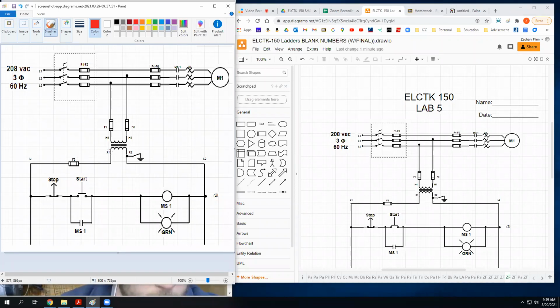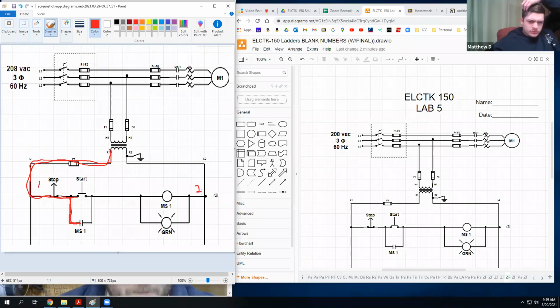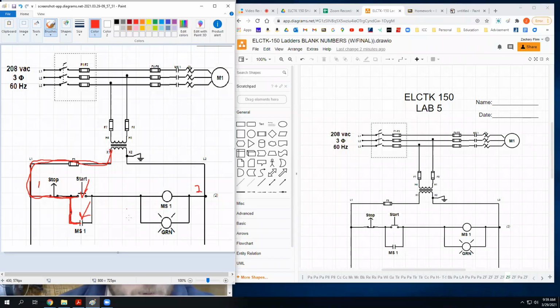Right now, in its de-energized state, if this was all hooked up and energized, I have 120 volts difference of potential on all of this right here. Right? And is any current flowing from left to right? Or from 1 to 2? No, because this is open and this is open. Correct? Yeah. Seal in contact maintains that current flow.